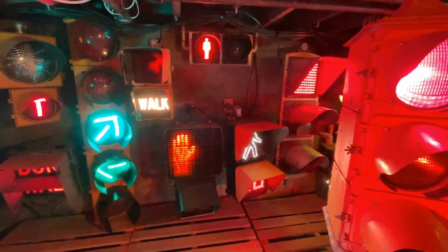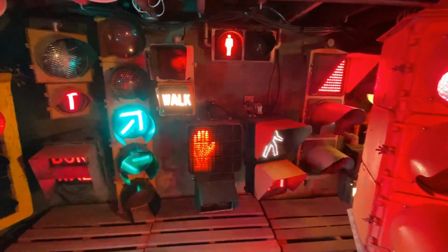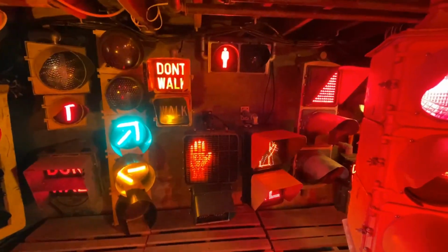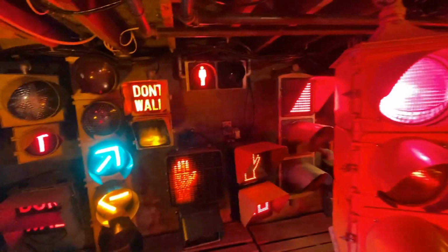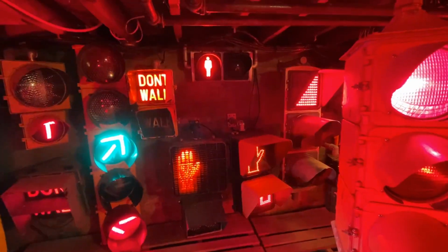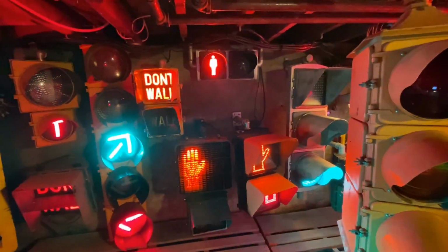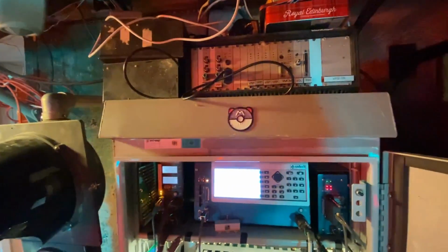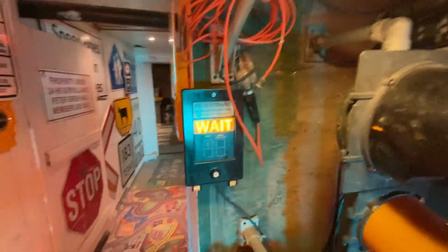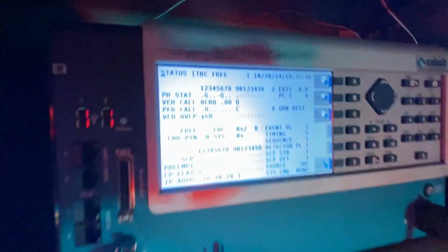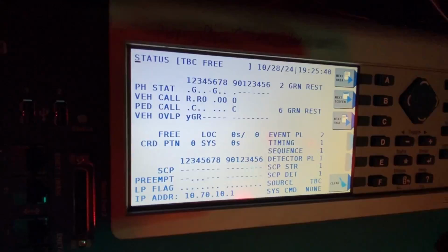And then it will also double serve in phase 4. When it's not cycling the phases, it will actually carry over to phase 4. Alright, now we're counting down again. Here we're going to bring up all the phases again. This one we'll always call the exclusive pedestrian phase. As you can see, 9 is in there.